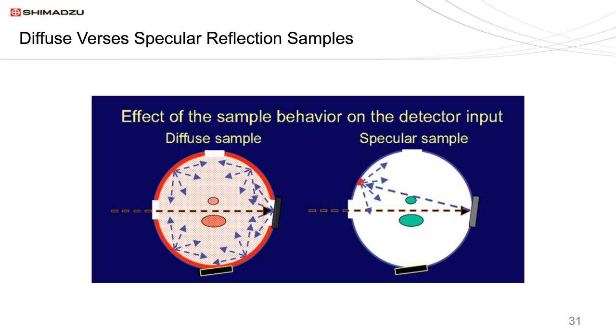Spheres have the ability to measure total reflection and diffuse reflection. For a sample with both a diffuse and specular component — something like a piece of wood with a shiny varnish — on the left you see the diffuse component being integrated by the sphere. On the right, the specular component also strikes the sphere and is integrated in total reflection mode. Depending on sphere design, there are ways of eliminating the specular to give diffuse only, by trapping out the specular light so only the diffuse component is measured.